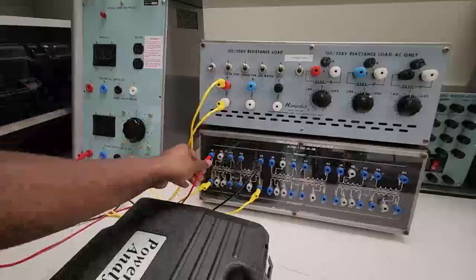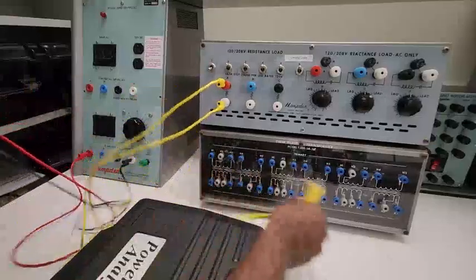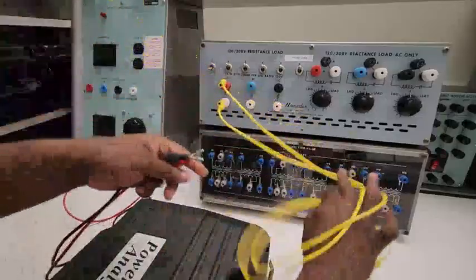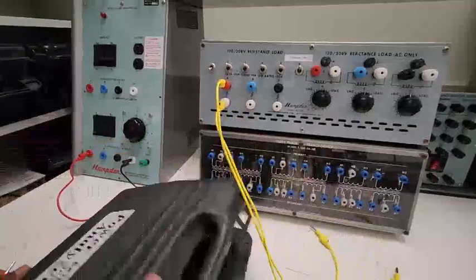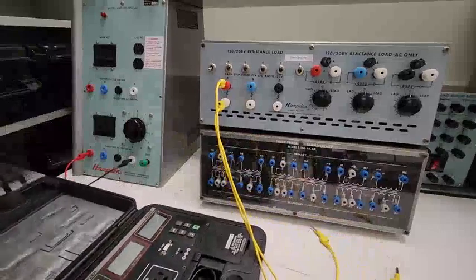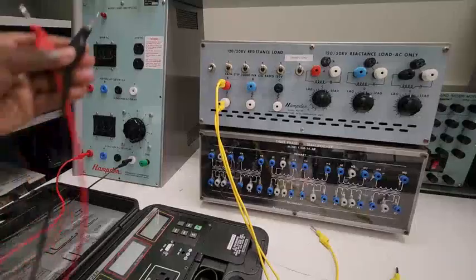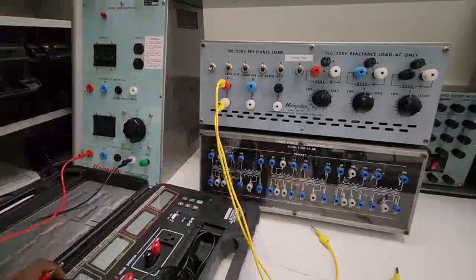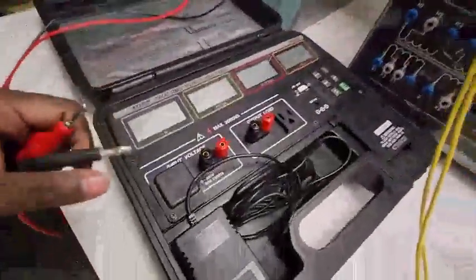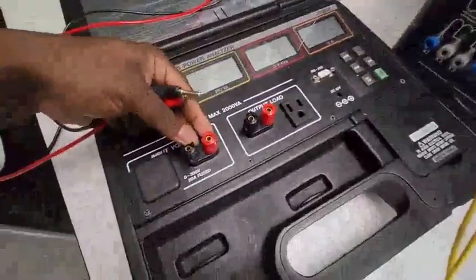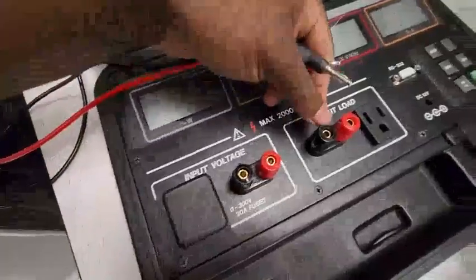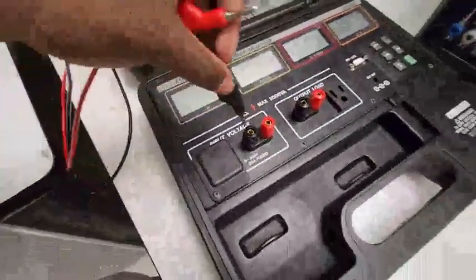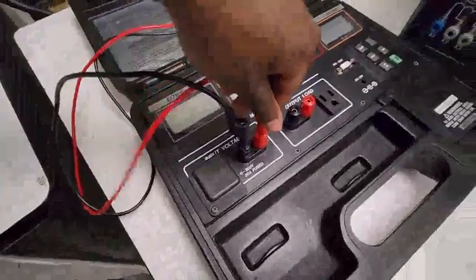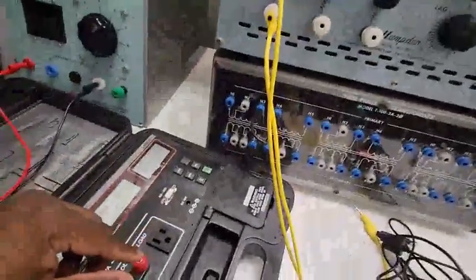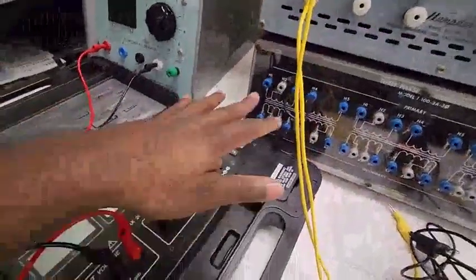If we want to connect the power analyzer, we need to get rid of all the previous connections. Let's open the power analyzer here and connect the power supply to it like so. There are four sets of jacks — two are for input, and two are for the output load. We're going to connect the inputs to the power supply, and the output will go to the primary side, so whatever current or voltage is supplied, it will measure.